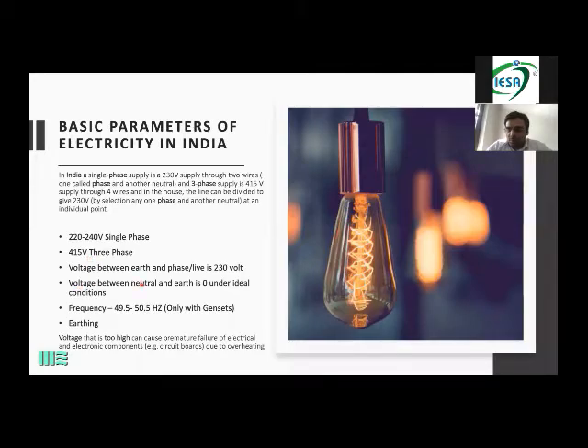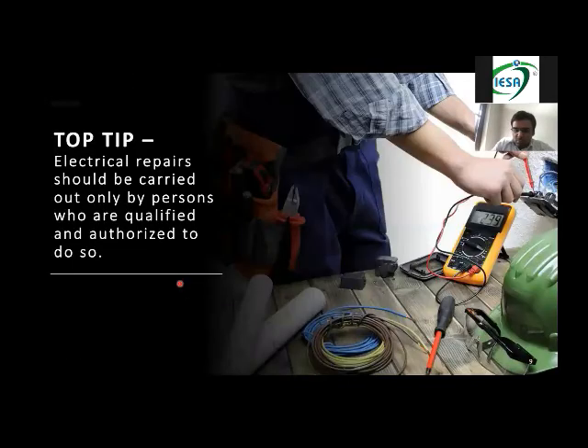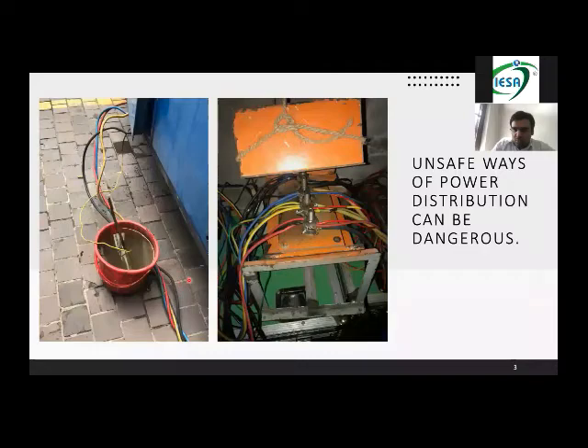Fourth is the voltage between the neutral, the black color wire, and the earth. We're going to talk about the earthing. Your earthing wire is outside the box. So basically you have 4 wires. We'll go back to the first slide so that it's easy for you to understand. These are the 4 wires. If you put the multimeter on black and blue, or black and yellow, or black and red, you will always get 220 to 240. If you check blue to yellow or red to this, you will always get 415 to 440. These are the voltages. Over here, there is no earthing. It is an open box.